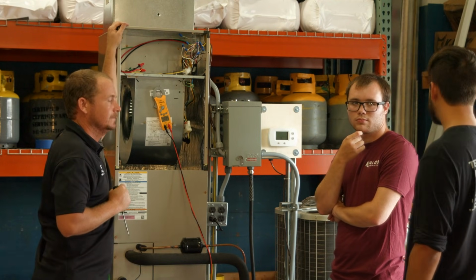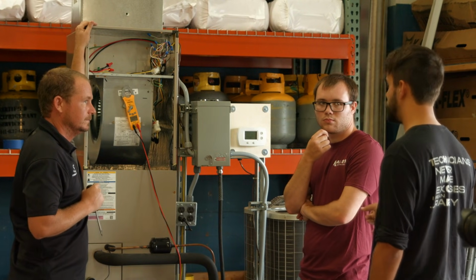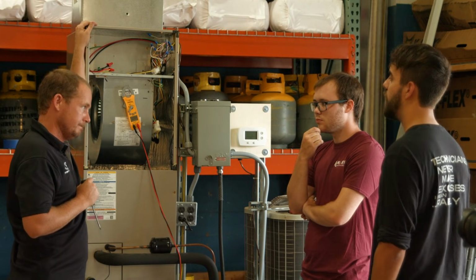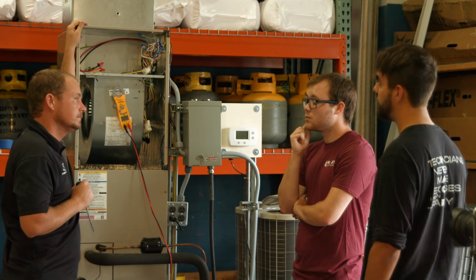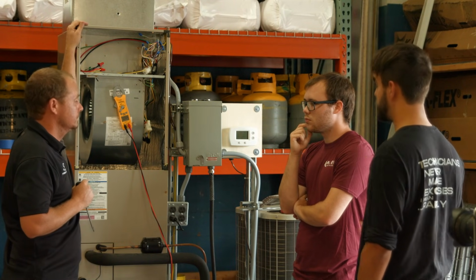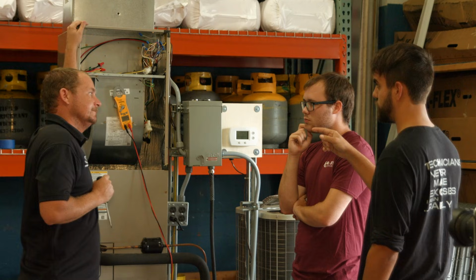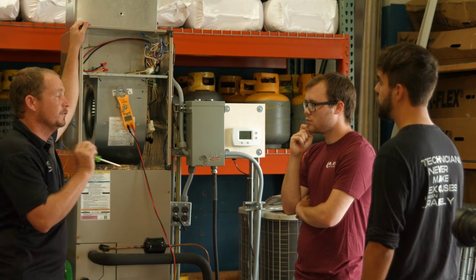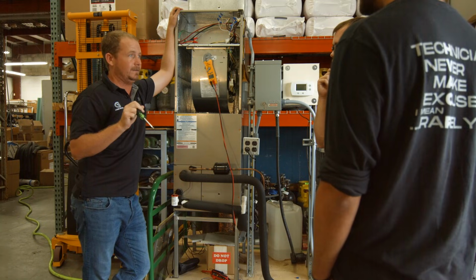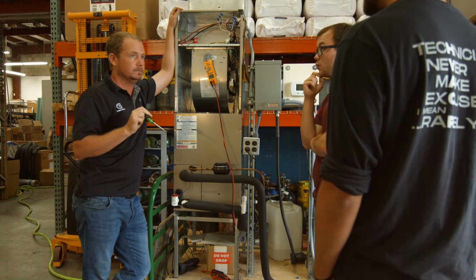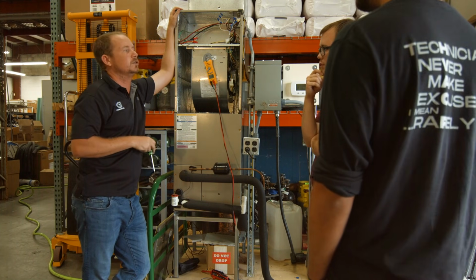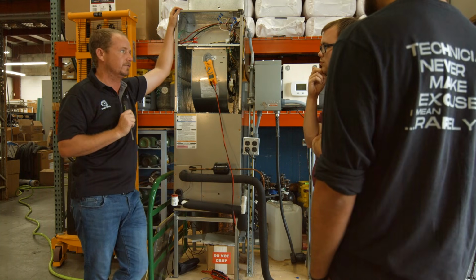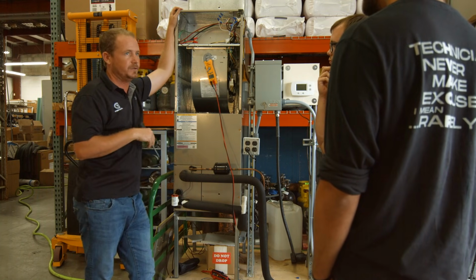First, I would check at the condenser to see if it's receiving 24 volts on the O wire. Okay. If it's not receiving it there, I'll follow it up to the air handler, see if the thermostat is sending 24 volts to the air handler. Right, now I don't know if we addressed this yet, but what kind of problem do we have here? What category of problem is it? We have an open. Correct. It's not a short, so that's what we're looking for is an open, which is good because we don't have to mess with fuses or any of that kind of stuff.